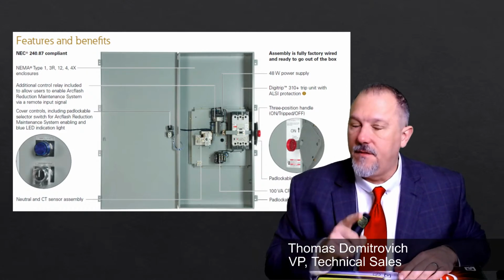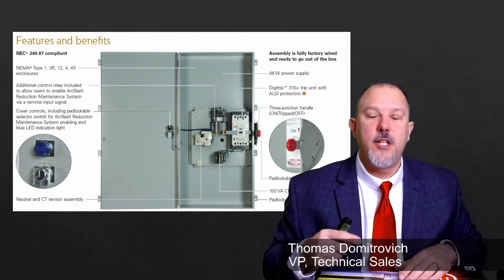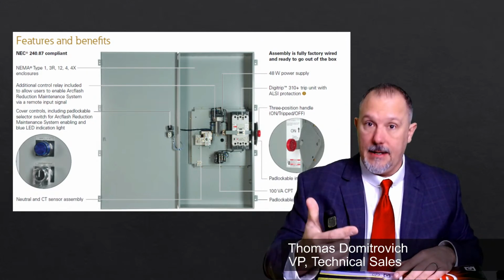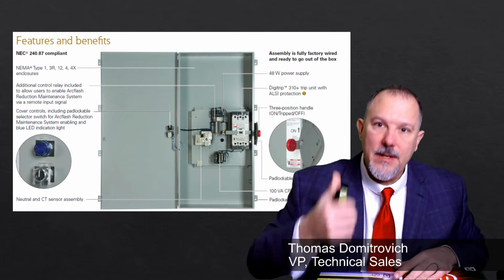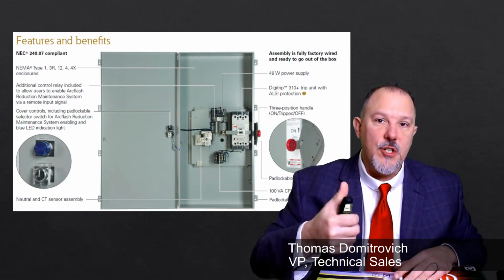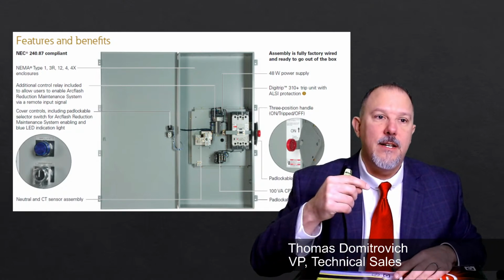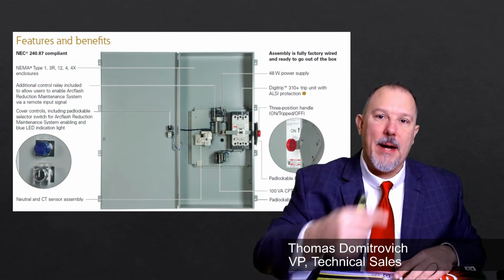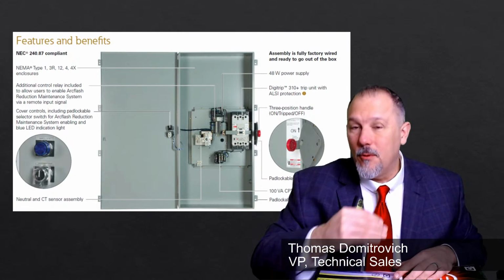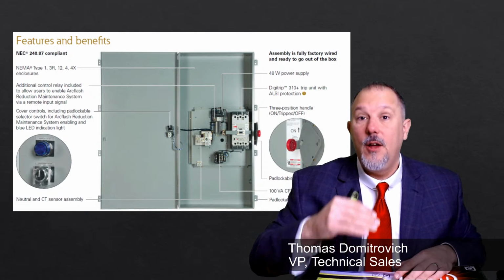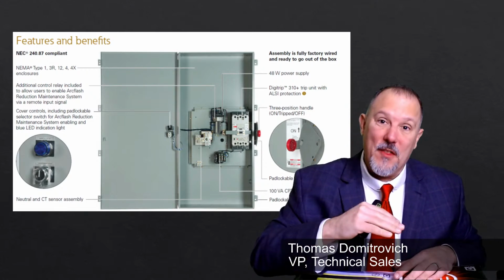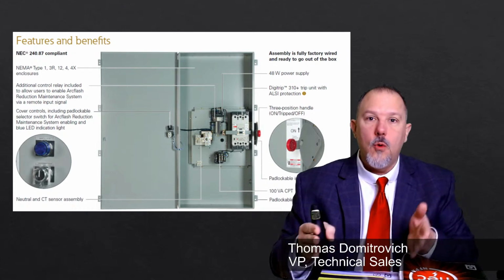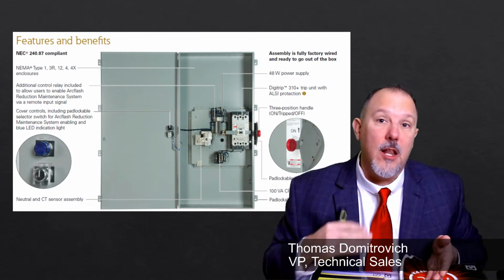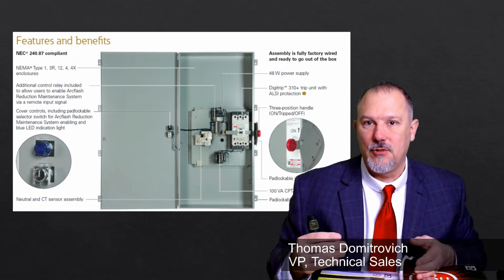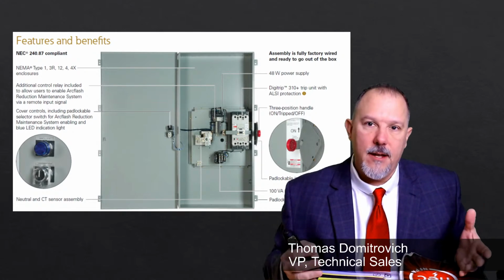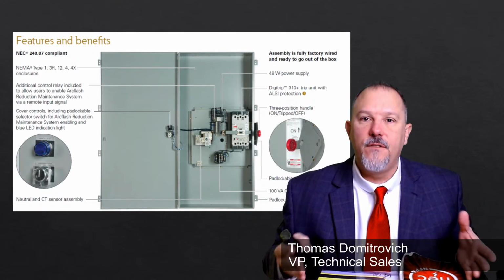Be mindful, what is incident energy all about? Current and time. Clearing of the arcing current is what you're trying to do. The further down you get into a power distribution system, the lower the fault current is, which means the lower the arcing current is. And at lower voltages, the arcing current is even lower than at higher voltages. So you could have a 600 amp device at 600 amps at 480 volts.